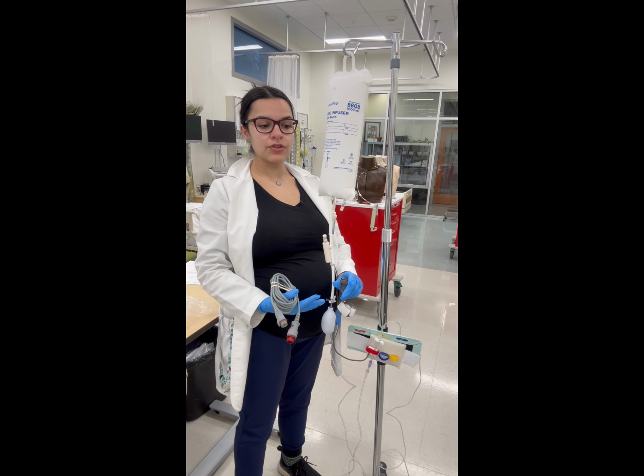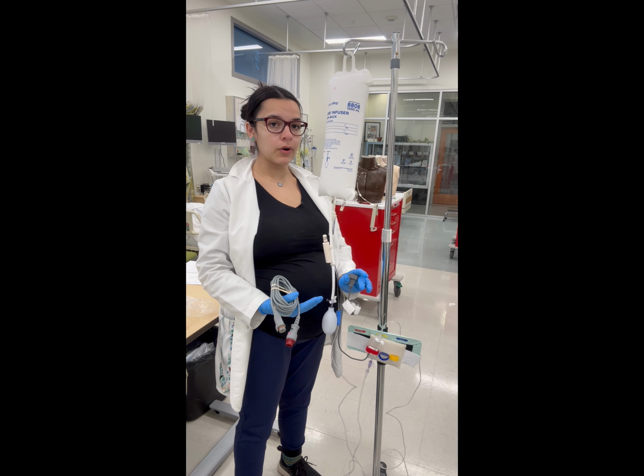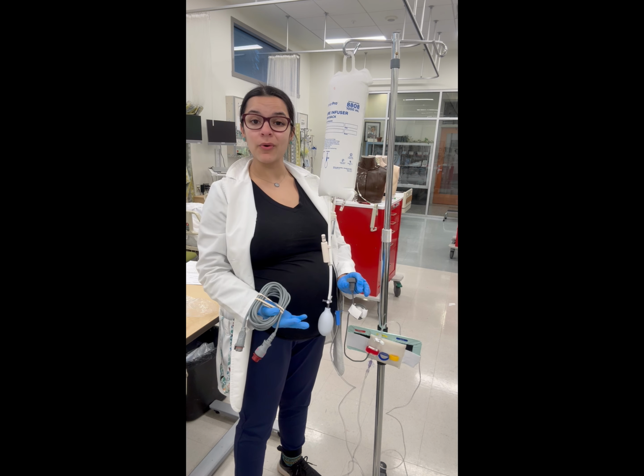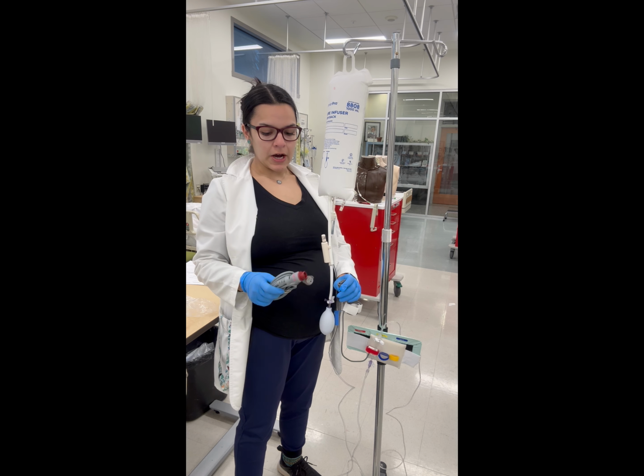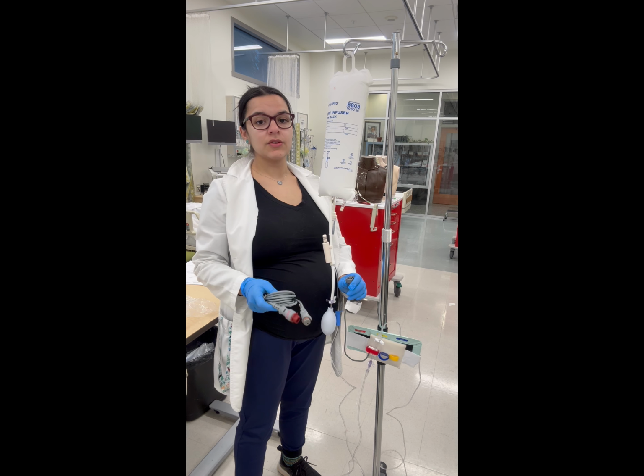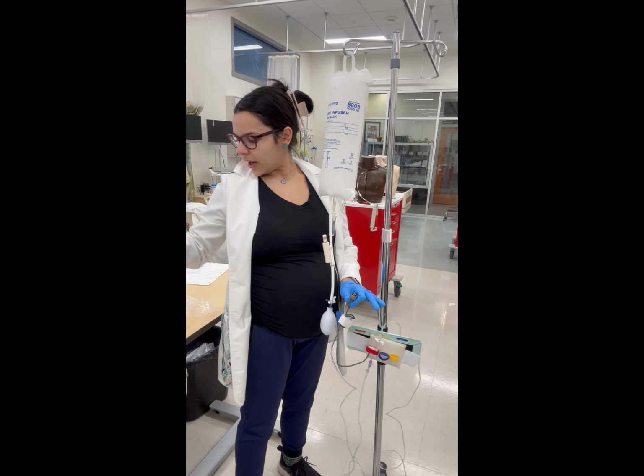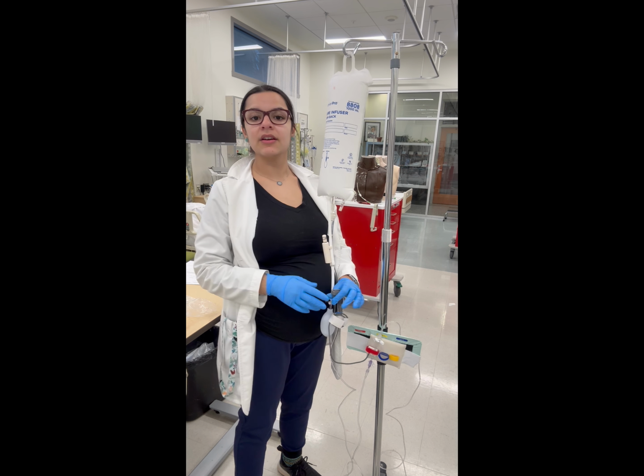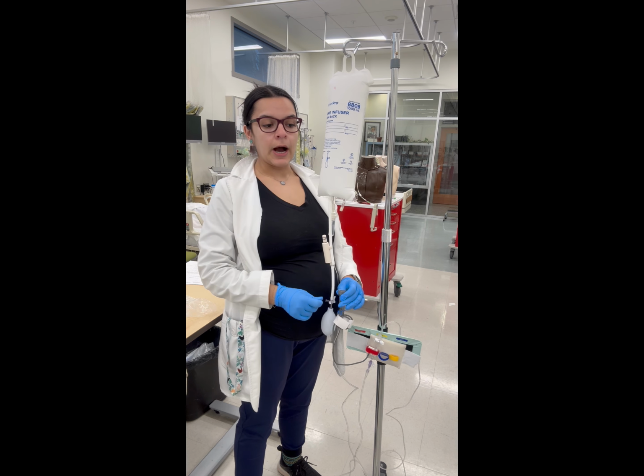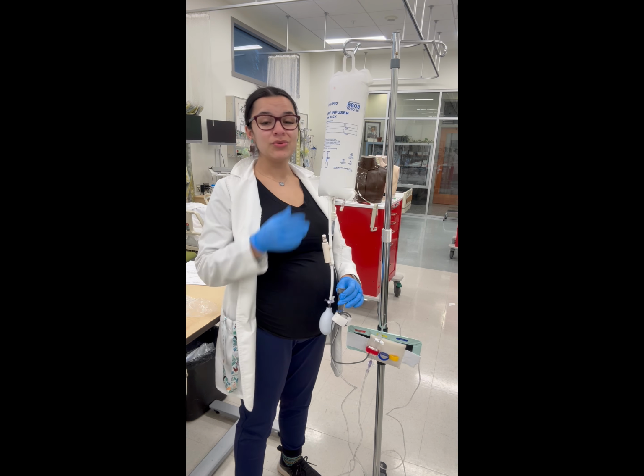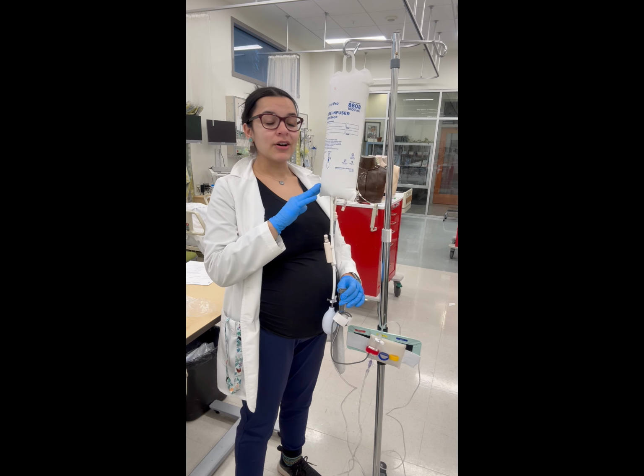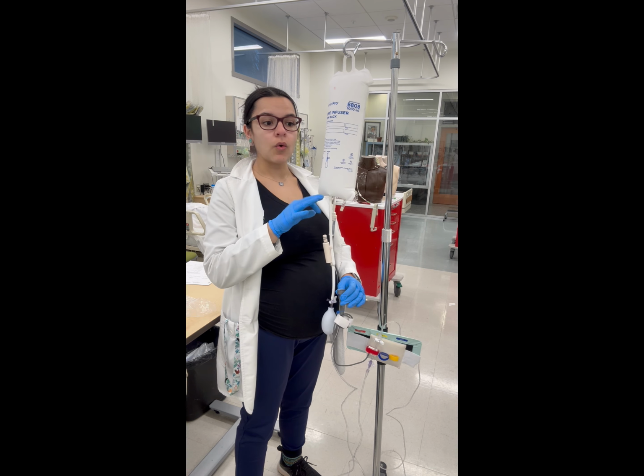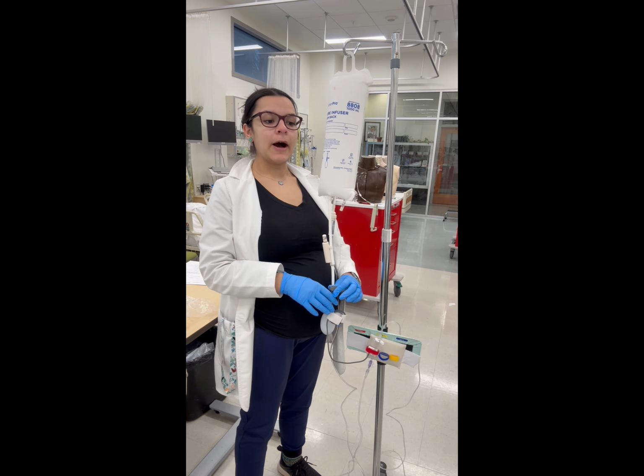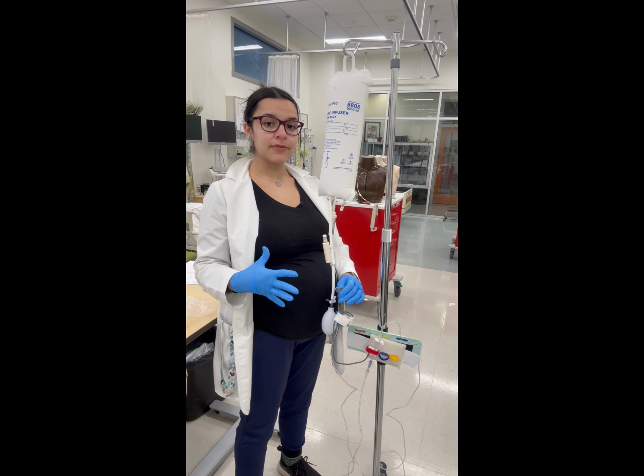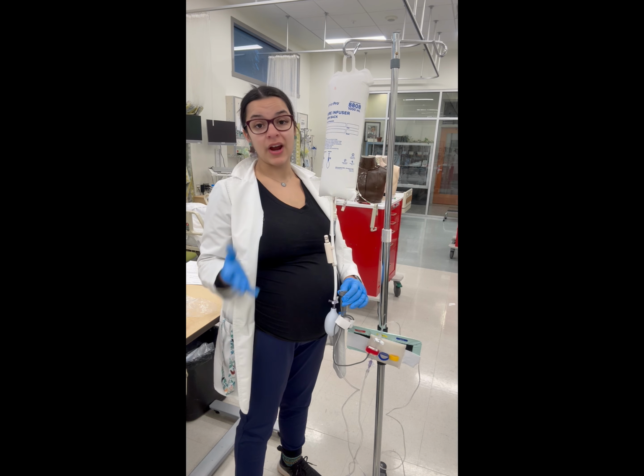And even if you attach this to the patient, you might get a waveform with no numbers, or maybe you get numbers with no waveform, vice versa. What we need to do at that point is zero the line. And whatever your facility's policy is on zeroing the line, just remember that every time you use the line, or if you have uncertainty in the numbers, or if you move the patient, you should be zeroing and flushing that line to make sure that your numbers are accurate, okay?